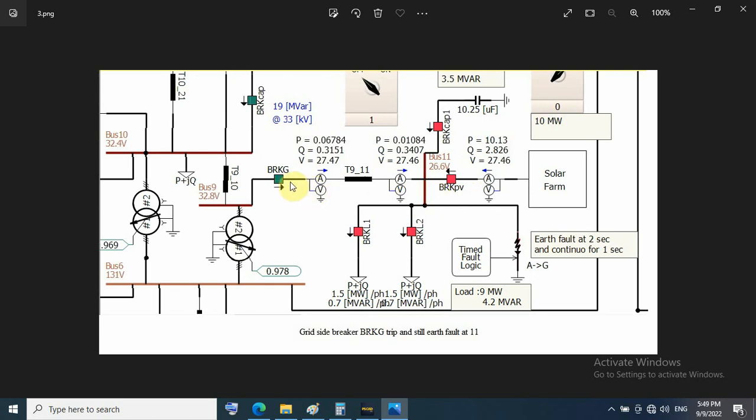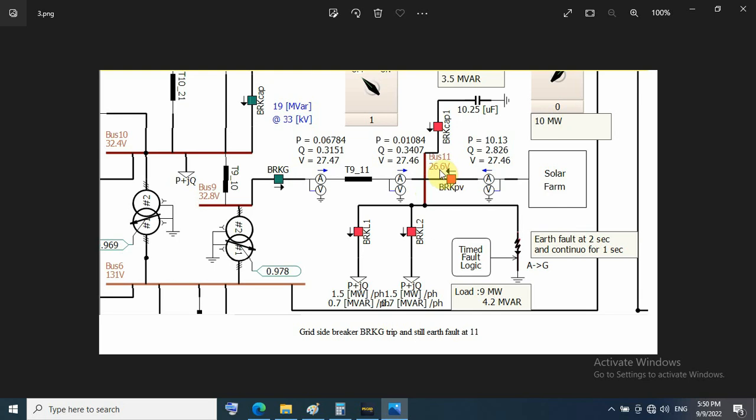Before fault clearing, the grid side breaker trips with earth fault protection. That means I lose the grid, and earth fault is still at bus 11. Now voltage decreases to 26.6 kilovolts.